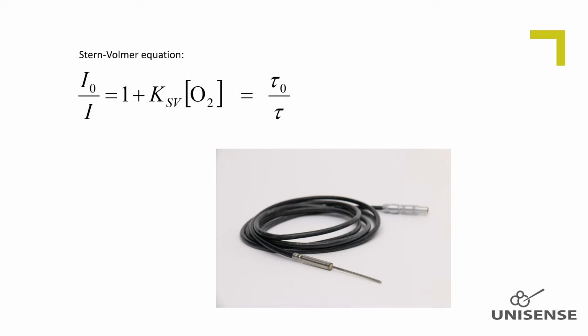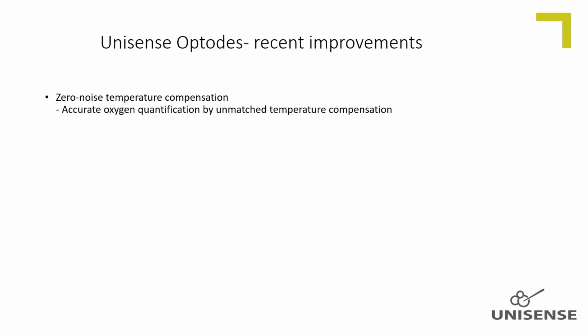Because the calculations need temperature input, a high signal quality is highly dependent on a high resolution temperature measurement. Low resolution temperature measurements will result in low resolution oxygen measurements. Therefore, Unisense has invested much time in finding the best possible temperature sensor to support the optode measurements. In case the setup in which the optodes are used is accurately temperature controlled, the temperature value can be entered into Unisense's logging software and no real-time temperature measurements are needed.